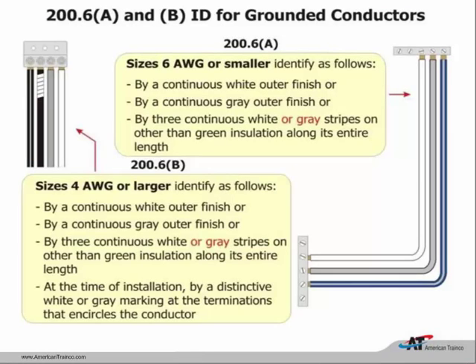In 200.6, identification for grounded conductors, they added a small but important change. For size 6 or smaller, it must be a continuous white or continuous gray—they're not allowing field identification; it has to be continuous. They previously allowed three continuous white stripes and have now added three continuous gray stripes on that conductor. For number 4 or larger, we are still allowed to identify the conductor in the field at the time of installation, and three continuous white or gray stripes are also allowed. Manufacturers now make wire in any color we want, making re-identification increasingly a moot point.